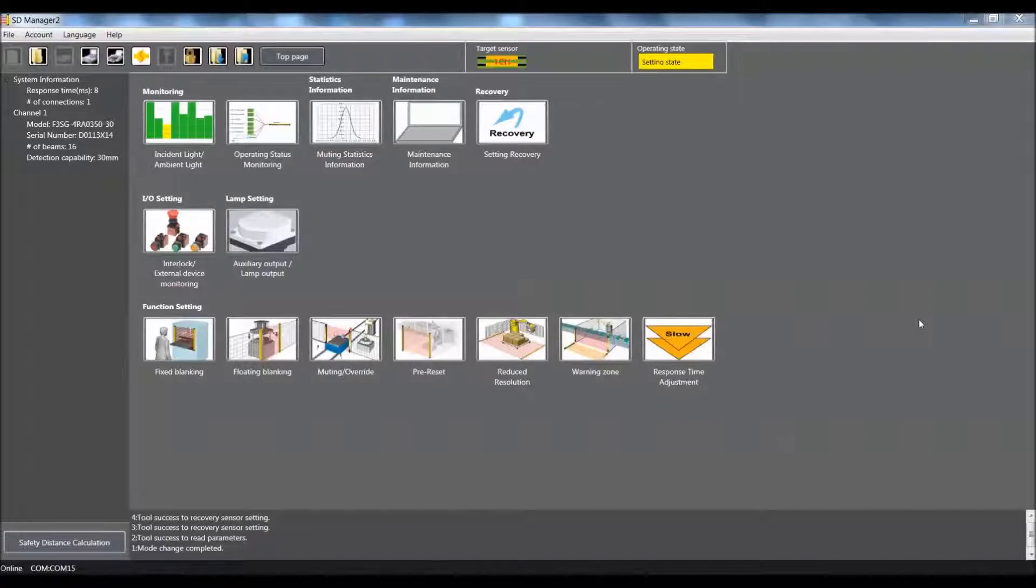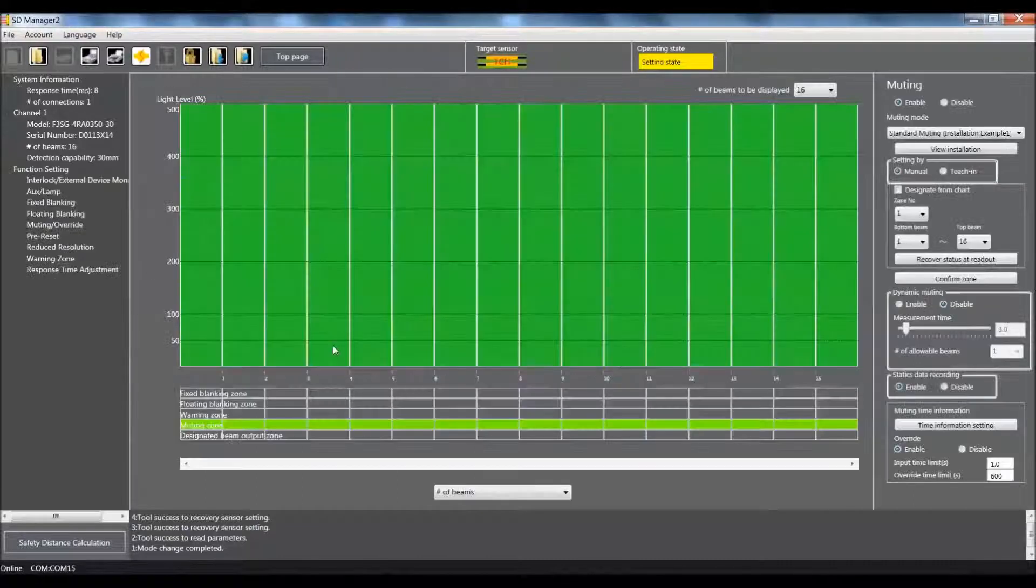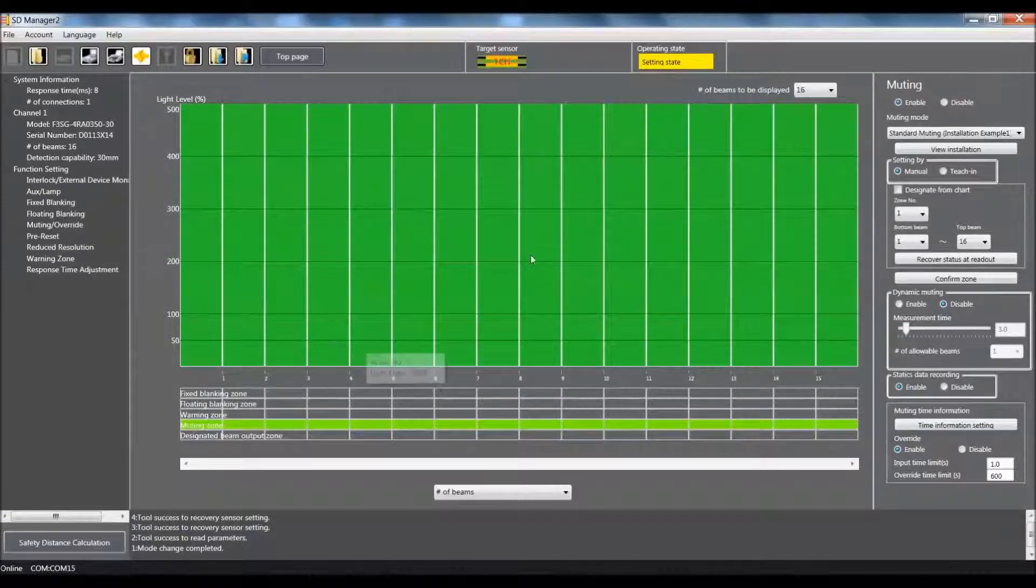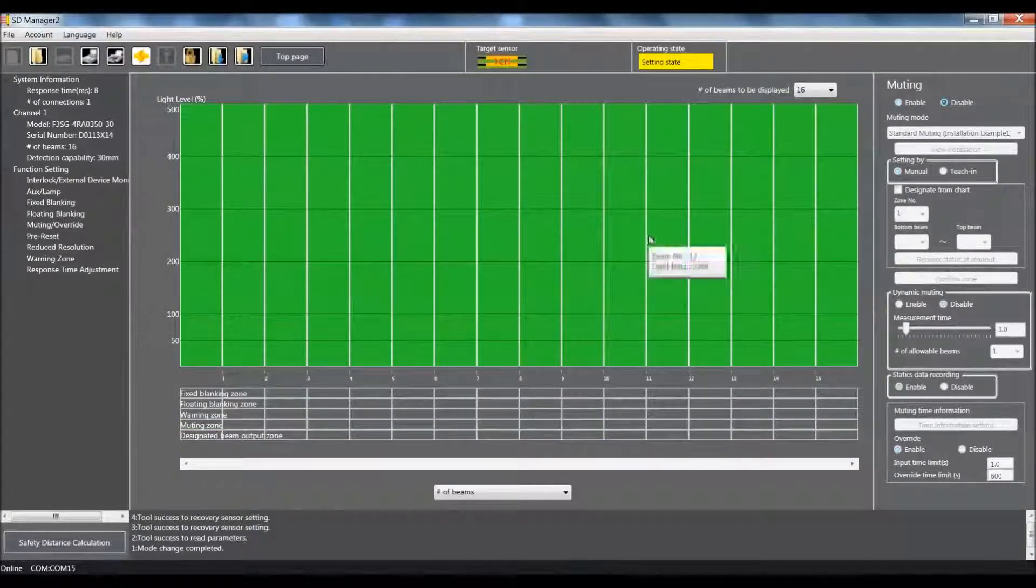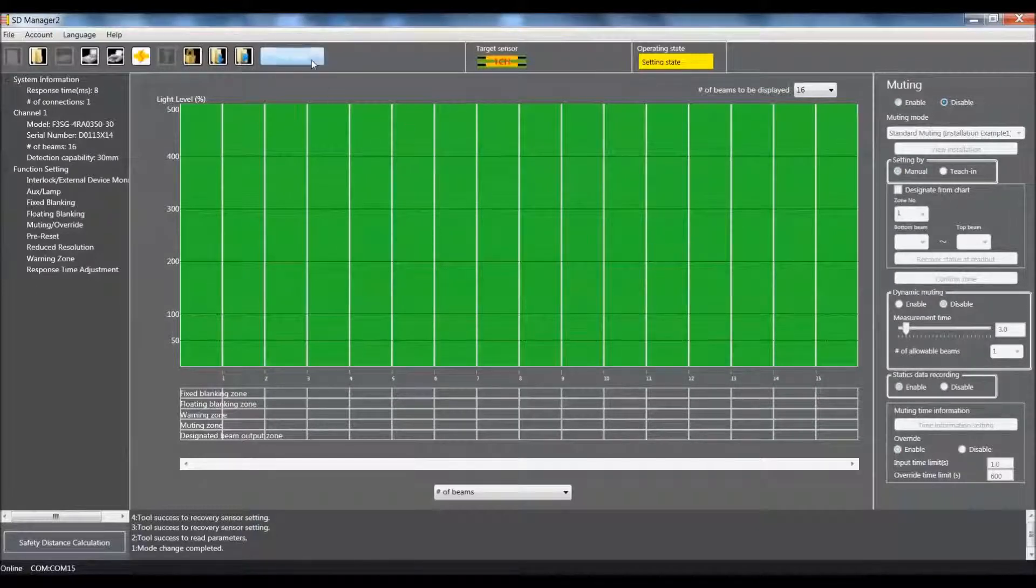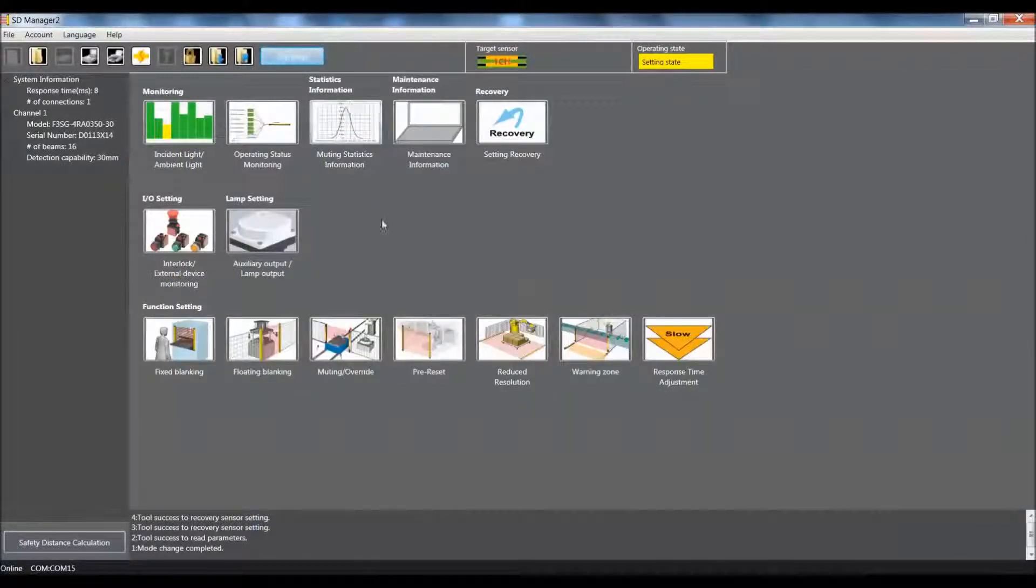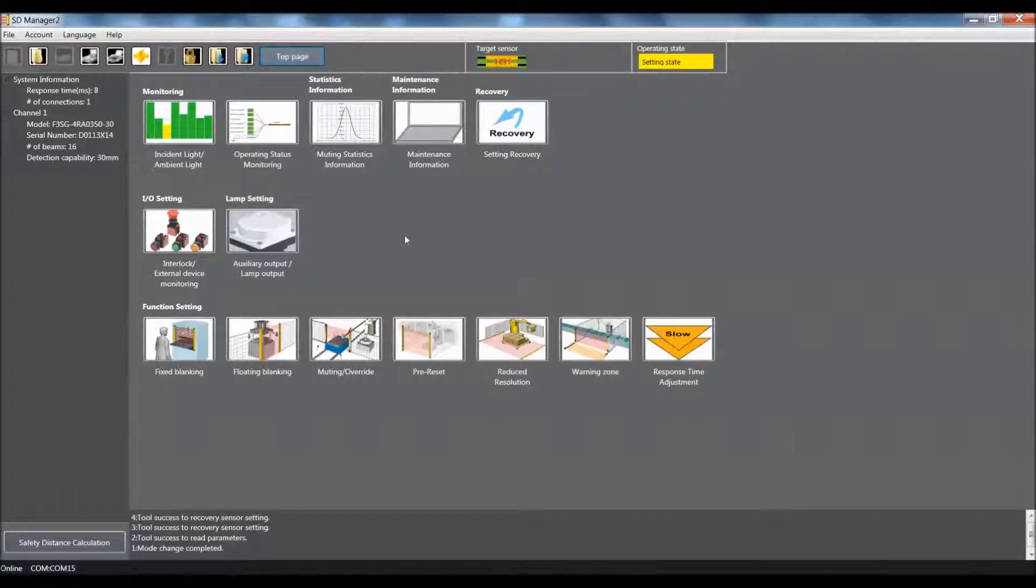Alright, first thing that we are going to need to do is come into the muting override. The reason for this is we need to disable the muting function. You cannot use the muting function in conjunction with the reduced resolution feature in the F3SG.